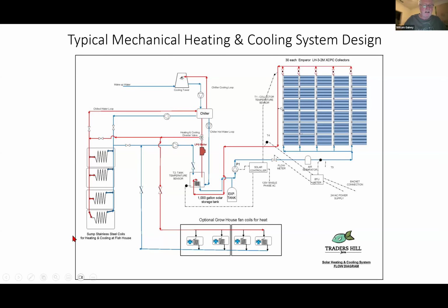So we would provide a sump system to be able to provide heating and cooling of the fish house, because they do have to have both heating and cooling, because the temperature of the water in the fish house is critically important to be able to keep the fish healthy and generating the poo necessary to fertilize the greenhouse. And then also we have the option to provide fan coil units for heating of the facility. And what temperature do we need in that heating? 100, 200, so there are opportunities for all of the technologies to participate in these types of systems.